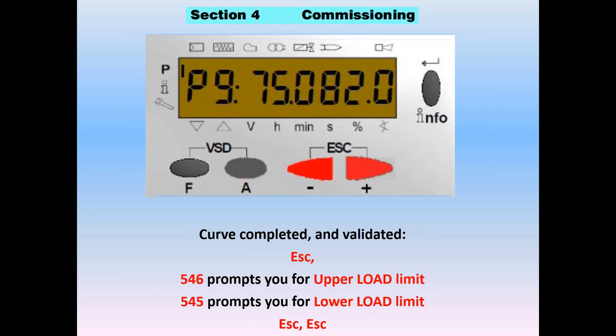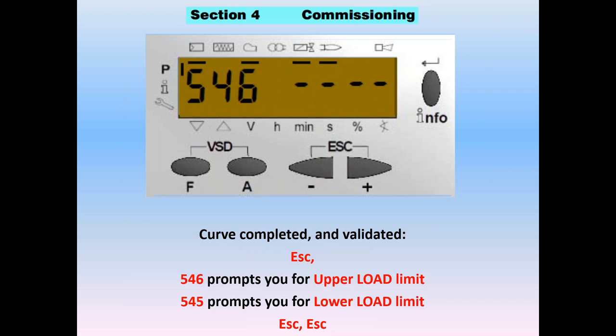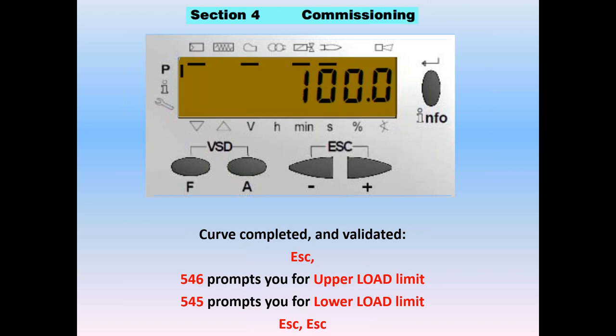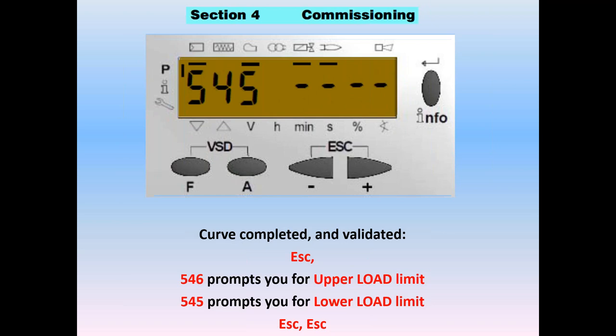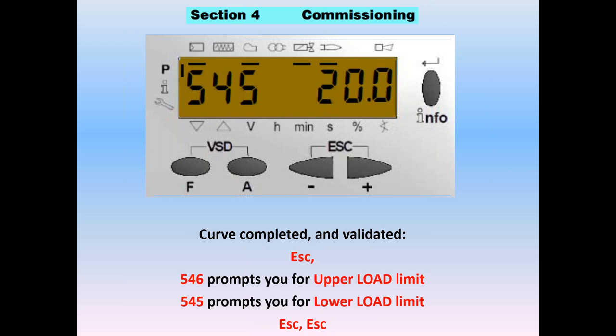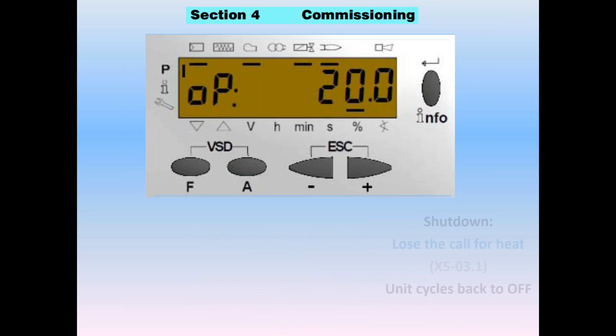Once the curve is completed and validated, press escape to get parameter 546 — it's asking for load limits. 546 is your upper load limit, 545 is your lower load limit. Go to 546, hit enter, get dashes, adjust to 100%, hit enter. Escape, and you see 546 with its value — just a parameter and a value, no index. Then press plus to get prompted for 545 — your lower load limit. Hit enter, adjust to 20%, hit enter, press escape. Now 545 has a value of 20. Escape and escape — now you're in operation at 20%, at the mercy of your load controller.